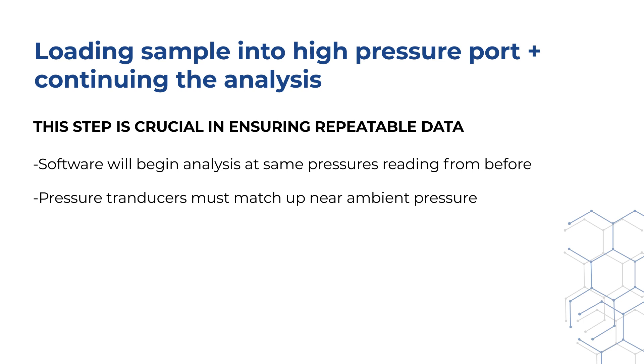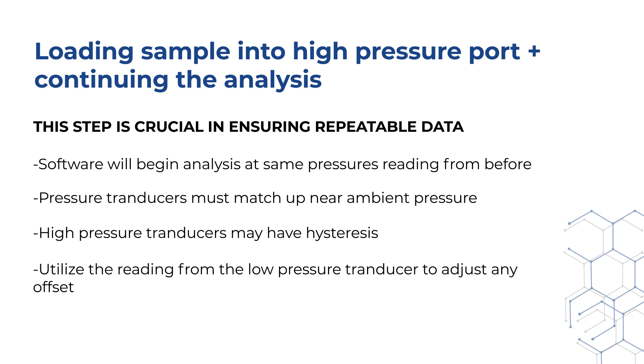We can make use of the reading of the low-pressure system when idle to adjust any offset in the high-pressure transducer. We will do this when we initiate the high-pressure analysis.